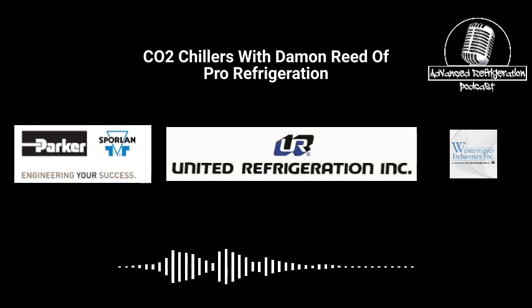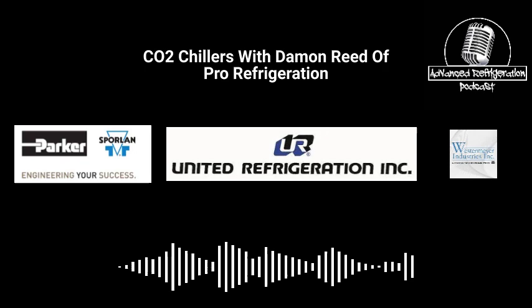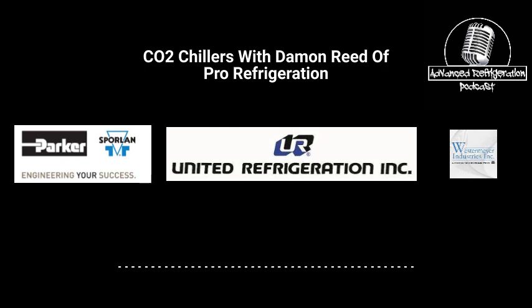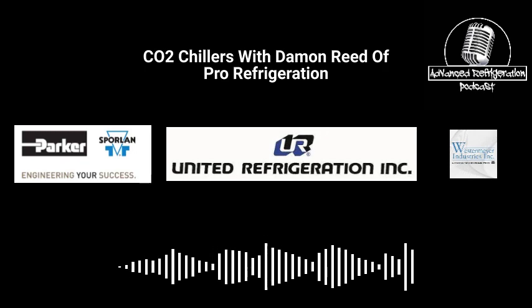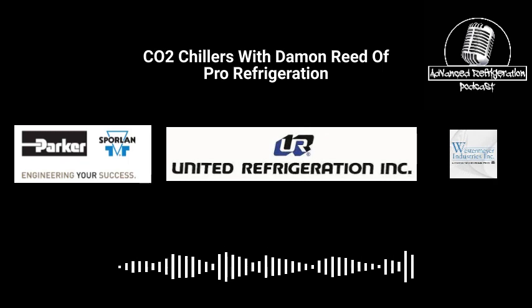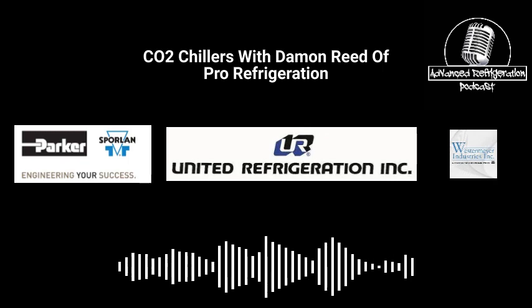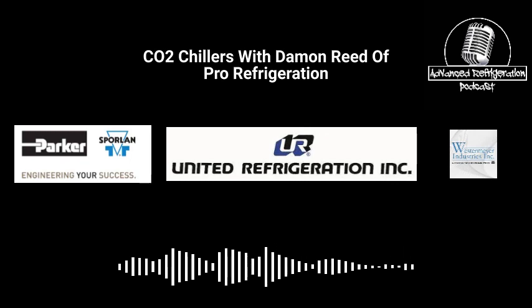Yeah, you could use the heat recovery for the rink, on the air handlers, to keep a constant load on the air conditioner so it doesn't get all humid in the place. Yeah, anywhere there's opportunity for utilizing hot water with a CO2 system with our heat recovery. You're just helping out the refrigeration circuit and taking advantage of all that waste heat that you could generate.